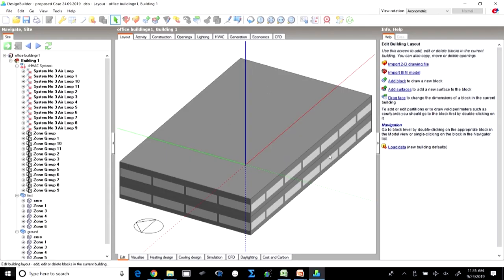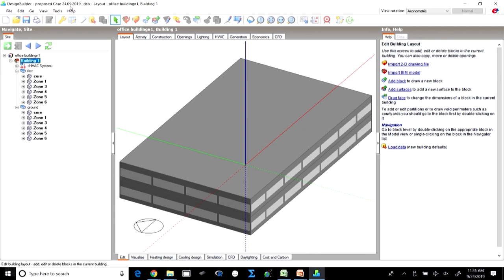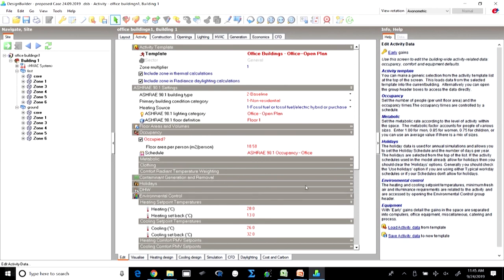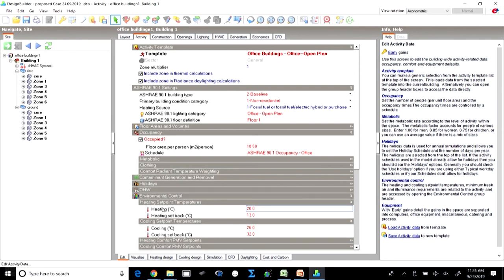Instead of the COP for heating and cooling of 0.8 and 1.8 respectively, we will use a higher coefficient of performance. The equipment power density we are going to keep the same. The activity and schedule will be retained as the same, and there is no change there. The heating and cooling set points will also remain the same — we cannot demonstrate reduction in energy consumption by changing set points, so whatever set points were in the base case will be the same in the proposed case.